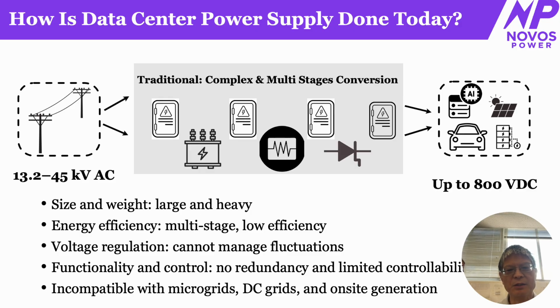Today, our power supply for data centers is realized in a traditional way. We get power from a medium voltage power grid through an iron core transformer, step down that medium voltage, typically between 4,000 to 45,000 volts, to a lower voltage around 480 volts. We rectify that voltage to DC, and then regulate that DC to supply power to the computing racks inside data centers.